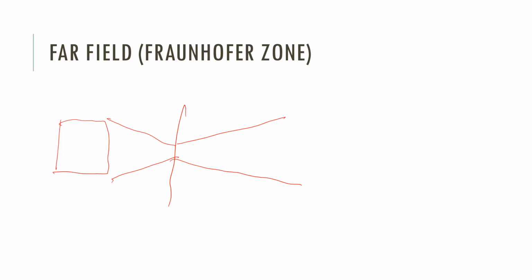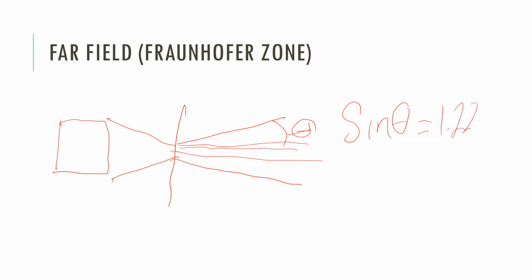What we want to describe is actually, from a straight line from the normal, what is this divergence? Okay, so if we draw straight lines from our transducer element, how far is it diverging? So we want to figure out this angle here. And to do that, we just go sine theta equals 1.22 multiplied by lambda on d.